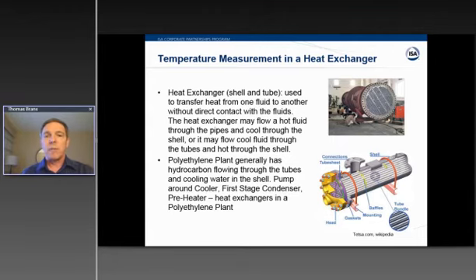So this is a look at a shell and tube type heat exchanger. The liquid that's going to be either heated up or cooled comes in through the header, runs through the tubes, and then comes out at a different temperature. The heating or cooling fluid goes in through the top connection and flows out through the bottom. So for this, let's talk about cooling off a liquid. At a polyethylene plant, you'd send in a hydrocarbon through the head, through the plenum, and then that would flow through the tubes, and then cooling water would flow over the tubes, come out through the bottom, and the hydrocarbons would come out the other end at a colder temperature.